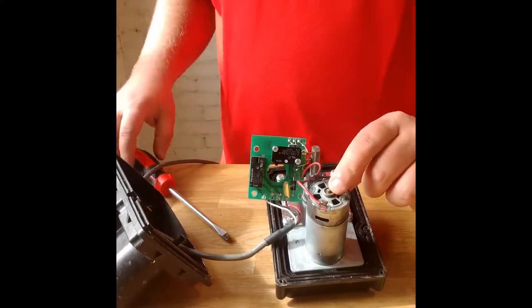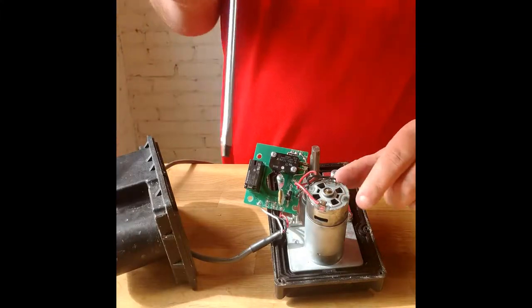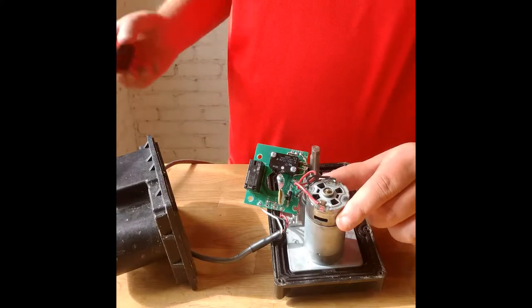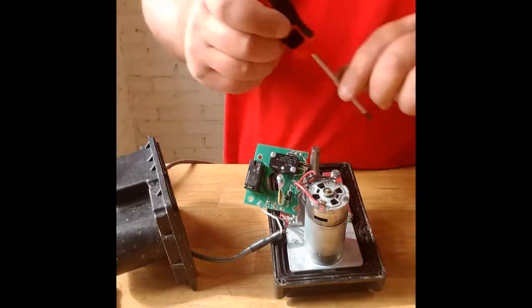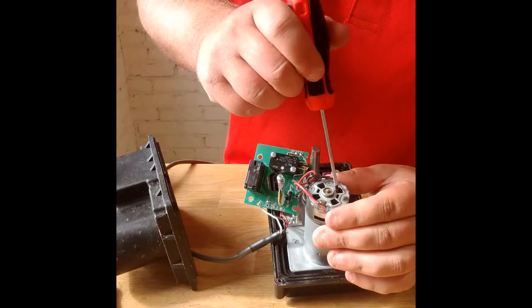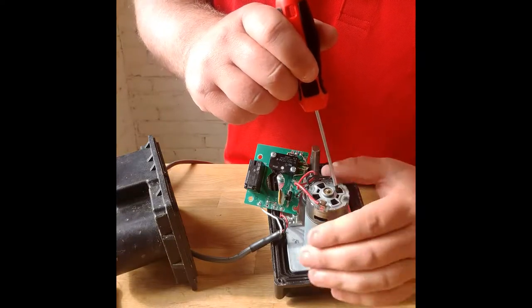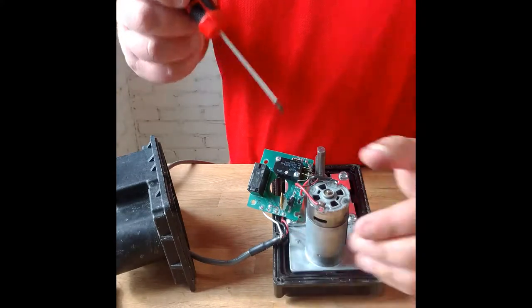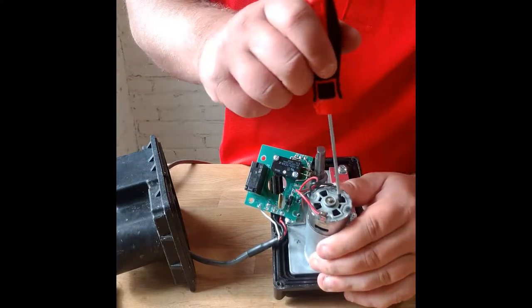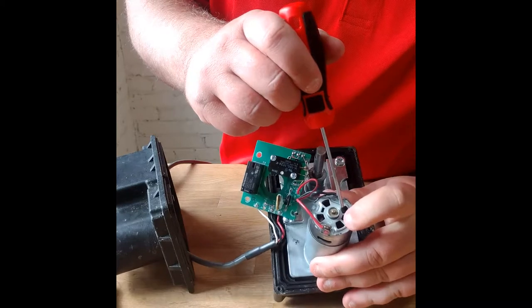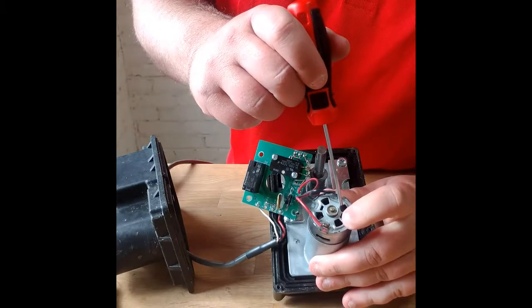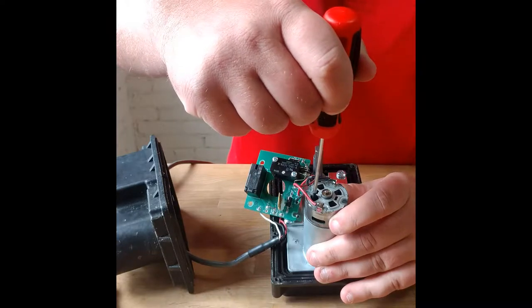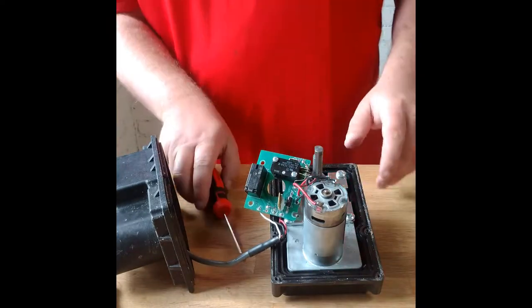The motor very rarely goes bad, but I'll try and tilt here. There's two brushes on this motor. It's a DC motor. And so you just take a screwdriver and you pry that out. And you can see how much of the brush is left. This motor has plenty of brushes left. Even after four or five rebuilds, the motor brushes are generally still good. So you always want to check to make sure the motor, since you have it out, if those brushes need replaced.